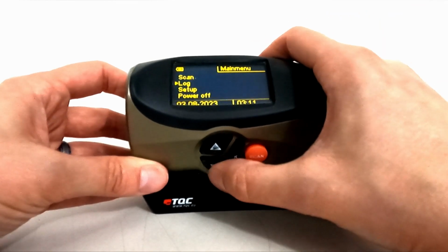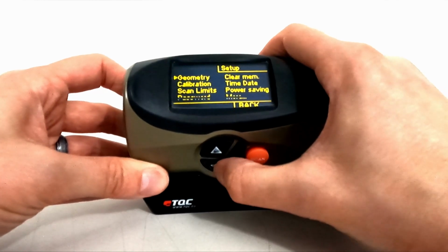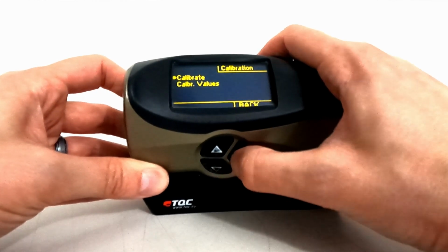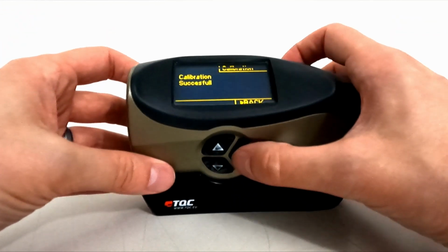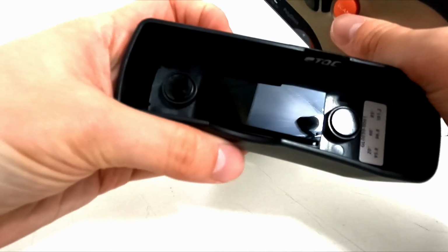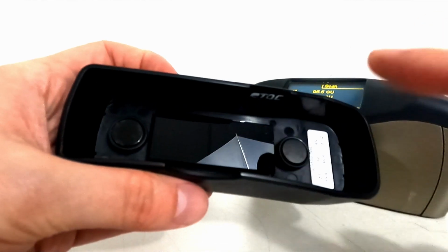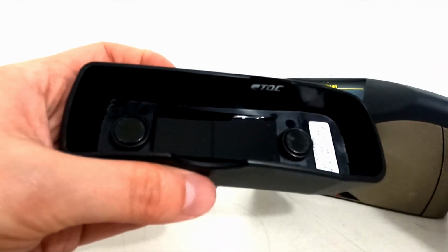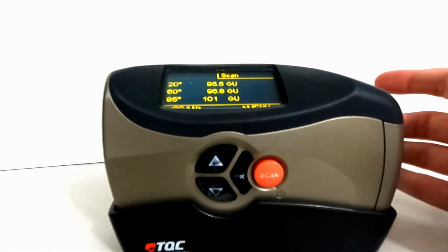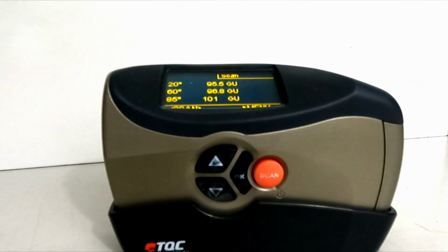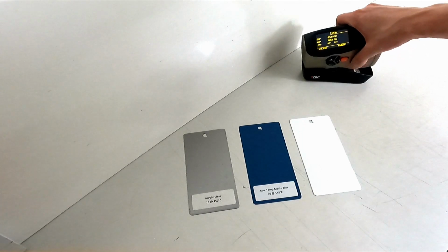Before using a gloss meter, you'll need to calibrate it by checking the calibration against a known surface, such as a highly polished black glass standard. These are included in the gloss meter's base. If the known surface readings vary from their expected results, the instrument will need to be recalibrated, preferably by the manufacturer. So, once you have your coated articles and your calibrated gloss meter, it's time to take some measurements.